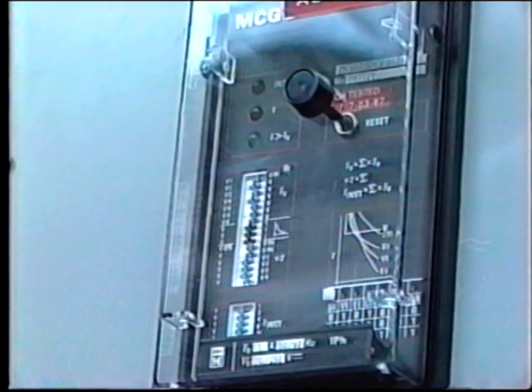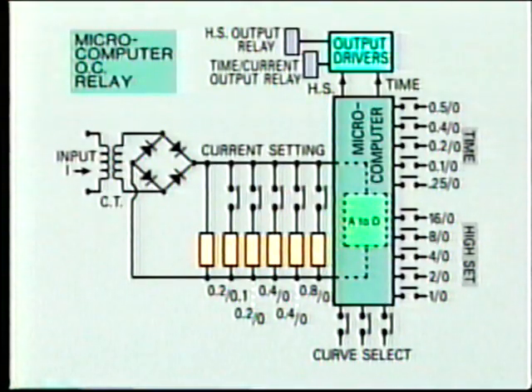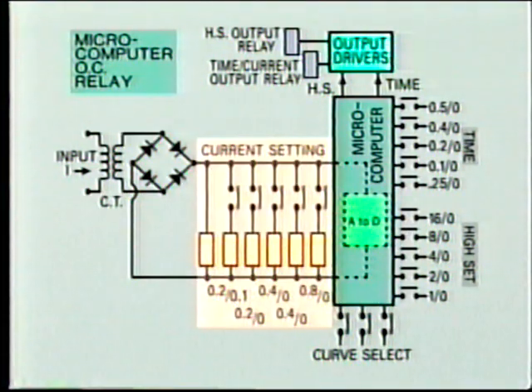A typical example of microprocessor relaying is this overcurrent relay, which is available as a single-phase unit, or 3-phase, or 2-phase and ground. The block diagram looks like this. Current input from the CTs is transformed and then rectified through a full-wave bridge. The current setting switches select the current range by adjusting the voltage drop across the resistors.